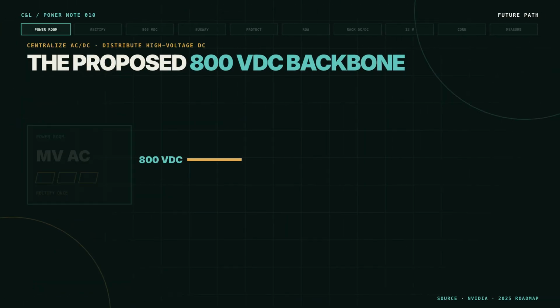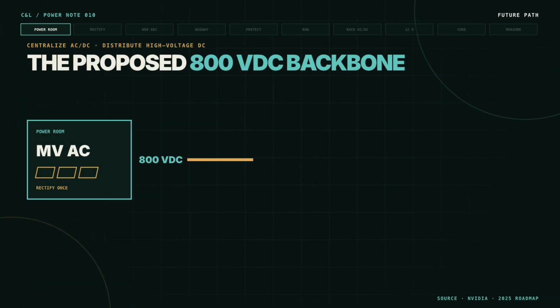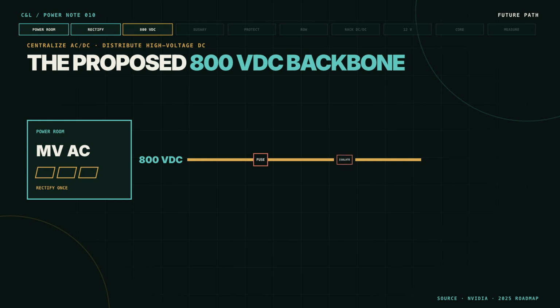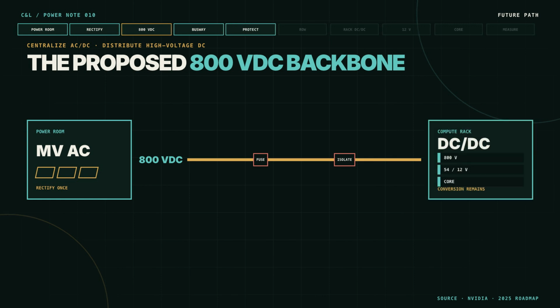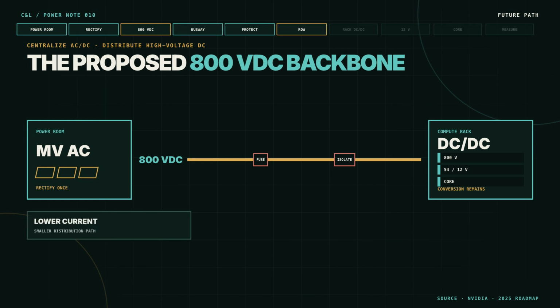The proposed architecture moves the main alternating current to direct current conversion away from each compute rack. In NVIDIA's diagram, medium voltage alternating current reaches a central power room, where large rectifiers produce an 800-volt direct current backbone. Protected busways carry it through the hall to the row and rack. Rack converters still step 800 volts down to 54 or 12 volts, then toward chip core voltage. The design does not eliminate conversion. It centralizes one stage and relocates bulky hardware outside the compute envelope.